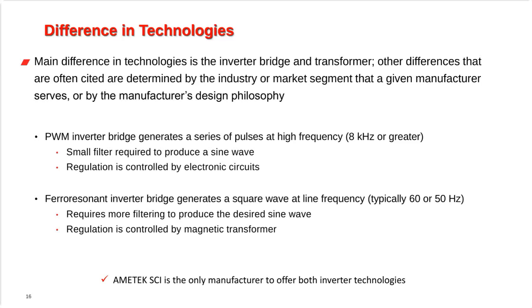Basically, the CVT, the constant voltage transformer, takes an input square wave and turns that into an output sine wave that can only go between a very tight regulated output. So let's say it's a 120 volt system. The regulation says that for varying inputs to that transformer, the output will remain steady at 120 volts, just through the inherent properties of a transformer, not through any control circuits. So I hope that explains one of the biggest major differences between the two.